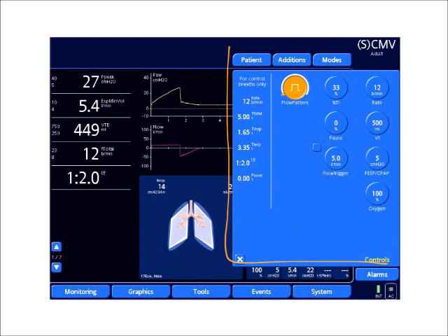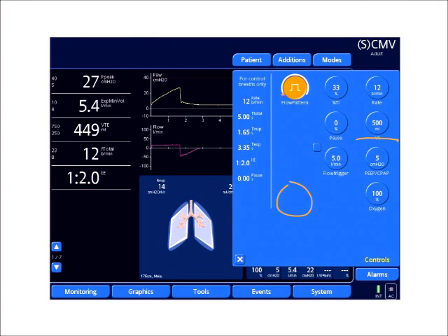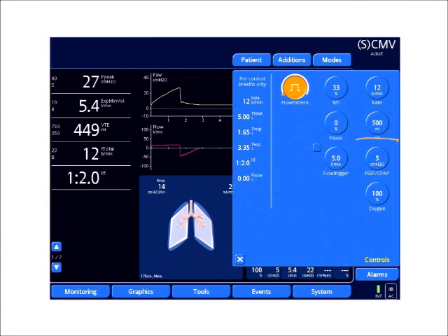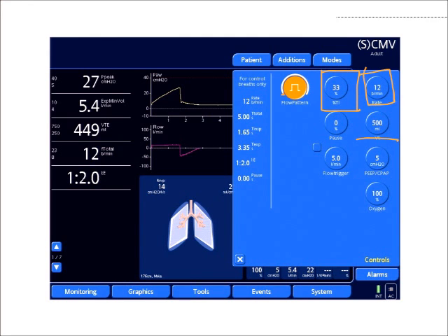Now here's another ventilator screen. If we look at this ventilator screen, there's a setting for tidal volume, but there is no setting for inspiratory time at all. However, we do have an inspiratory time percent setting, which based on my respiratory rate setting is going to calculate the inspiratory time for me.